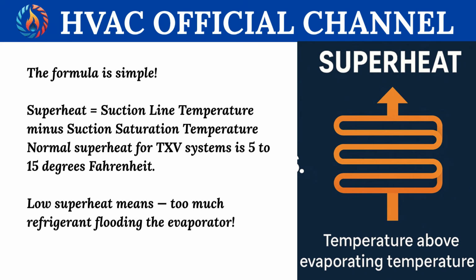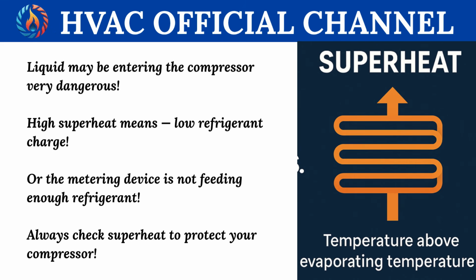The formula is simple. Superheat equals suction line temperature minus suction saturation temperature. Normal superheat for TXV systems is 5 to 15 degrees Fahrenheit. Low superheat means too much refrigerant flooding the evaporator. Liquid may be entering the compressor. Very dangerous. High superheat means low refrigerant charge, or the metering device is not feeding enough refrigerant. Always check superheat to protect your compressor.